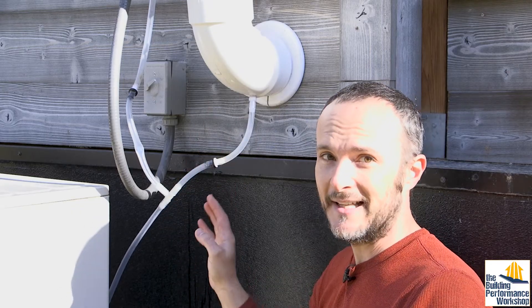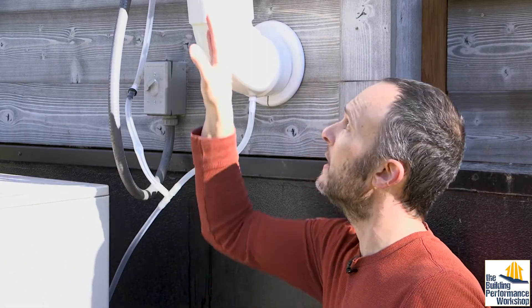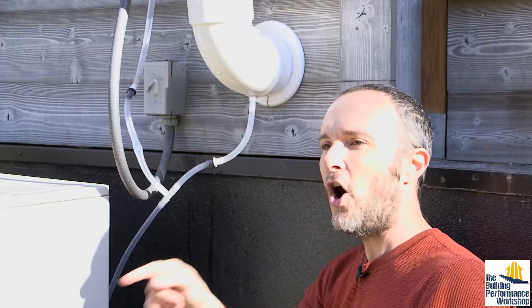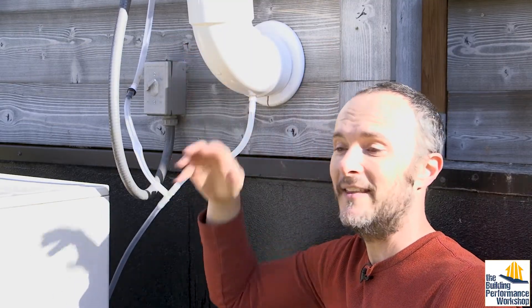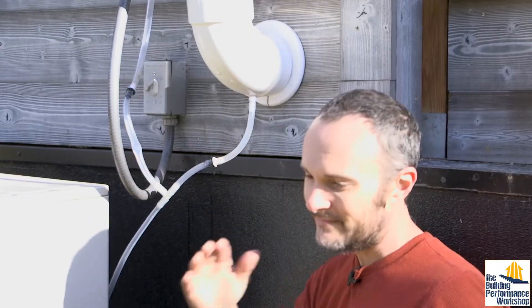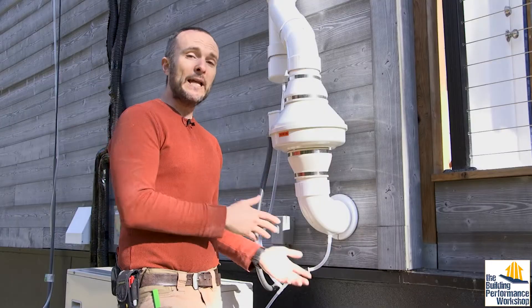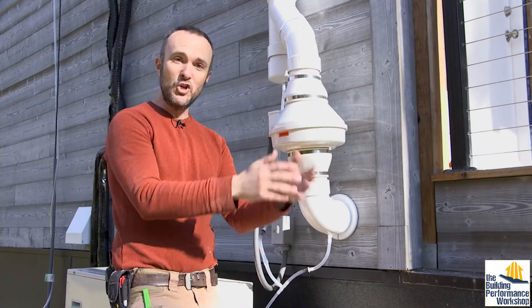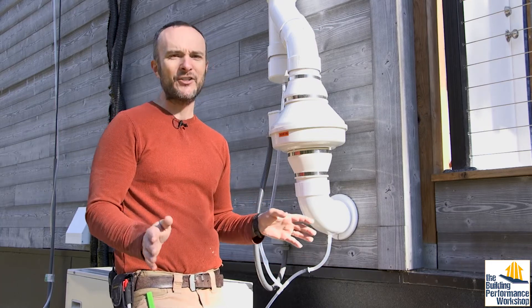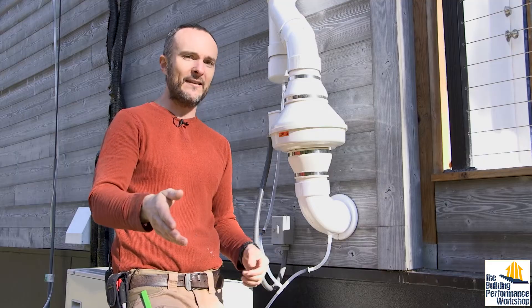Grace would like me to address why none of this is insulated — it's because when you think about the heat flow and the moisture related to that, we're not worried about any of this as long as you can take care of the condensation that does happen with these pipes. These pipes are the replacement for insulating everything to within an inch of its life to make sure the temperature of the pipe itself matches the temperature of the air being sucked underneath the slab. You can do it either way — this way happens to be a lot cheaper and a lot less time intensive. If you like what this system can do, it's pretty easy to plan into any new build. It's somewhat more difficult on an existing home because what's underneath the slab might just be packed dirt, which is really hard to suck air through — but you can do it if you use the testing protocol shown in the previous Fantech video, which is linked in the description below.